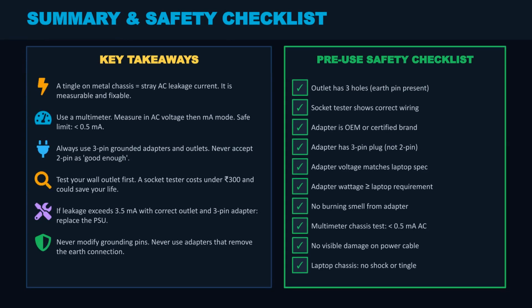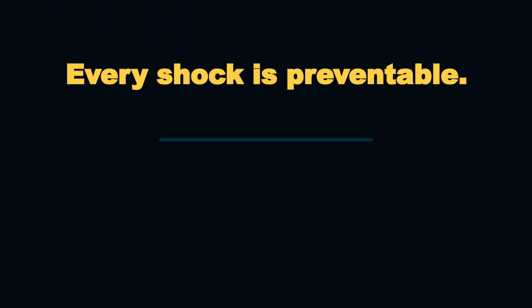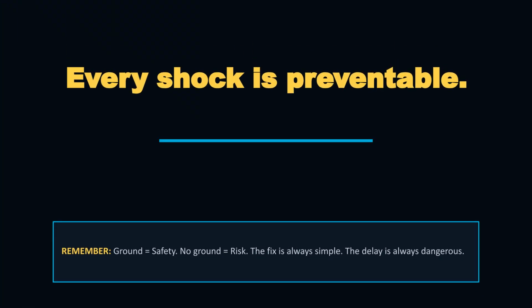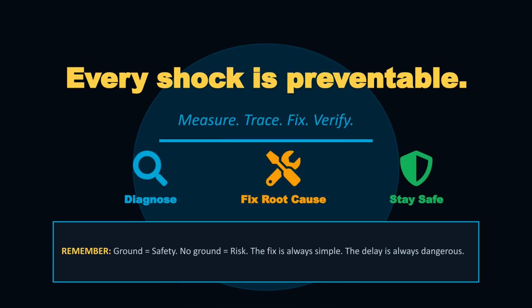Key takeaways include using a multimeter, staying under the 0.5 milliampere safety limit, and never using 2-pin adapters. Use the pre-use safety checklist to ensure your outlet is properly wired, your adapter is certified, and the leakage is safe. Every shock is preventable. Remember, ground equals safety, no ground equals risk. The fix is usually simple, but delaying it is always dangerous. Measure, trace, fix, and verify to ensure safety.